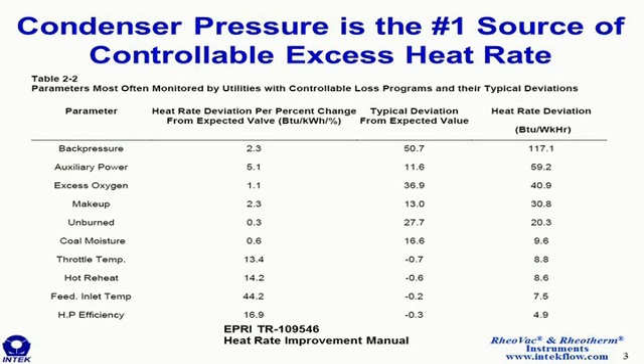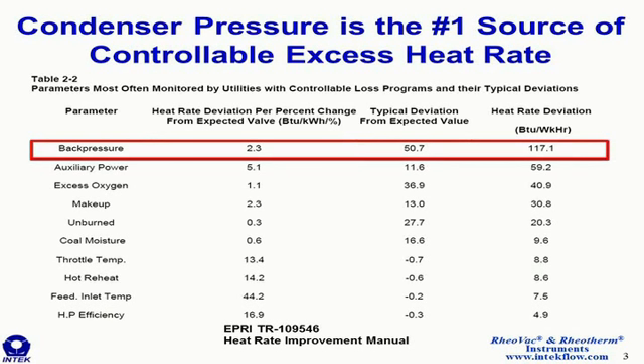And this table indicates to us why he gave that advice. This table is from the EPRI Heat Rate Improvement Manual. It lists the parameters most often monitored by utilities with controllable loss programs and their typical deviation. And you can see right away what tops the list is condenser back pressure. And not only does it top the list, but the typical deviation from the expected value is nearly twice that of the next highest item on the list. So the condenser is often a worthwhile component to study and improve, and improving it can significantly reduce heat rate or increase generation.